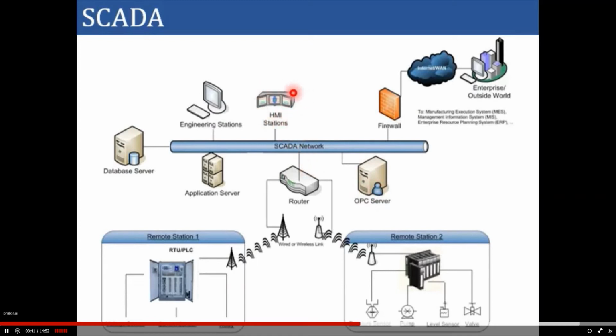Now HMI is nothing but Human Machine Interface, where the operator sits and sees the single line diagram of the power system network integrated with the data from RTU. RTU data is displayed on the HMI, where the operator keeps observing changes in voltage, current, and various parameters, and accordingly takes action to protect the system from abnormal activities. If a fault happens, the operator can initiate a command which goes back through the router to the RTU, and then to the relays, so the relay can operate and isolate the network.